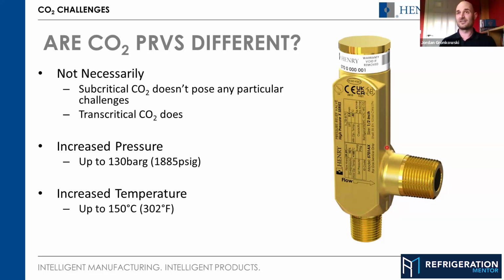Which again has an impact on us as valve designers. You have to look at the rigidity and the structural integrity of the valve at those pressures. A thing that comes into consideration there is the seal material as well. You tend to find most high pressure CO2 valves are Teflon or a derivative thereof in the seal material, whereas at lower pressures you can get away with softer seals with better leak tightness, because there is not as much force acting on the seal, because the valve's not set quite as high.